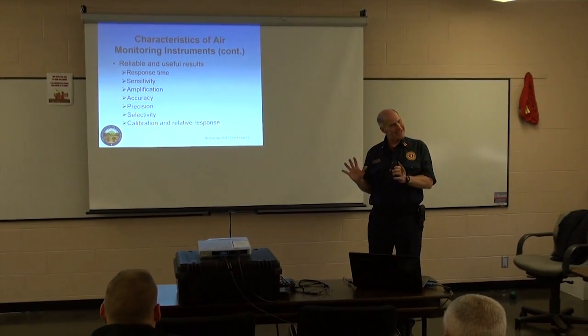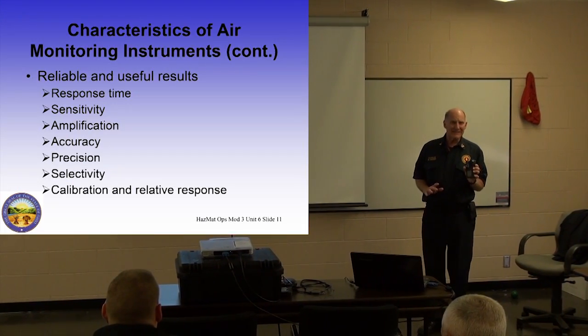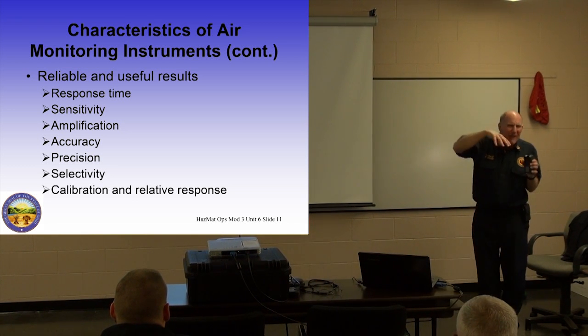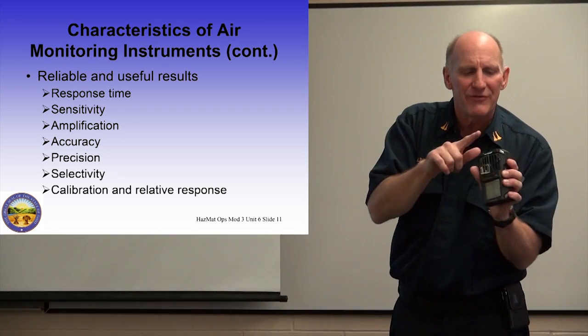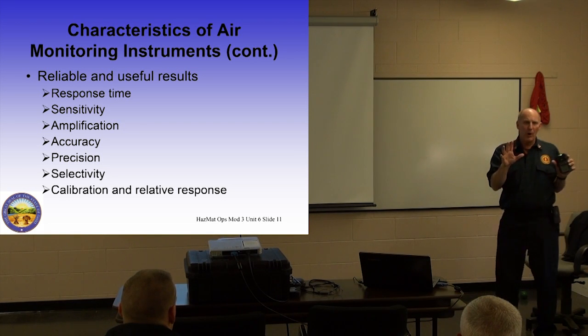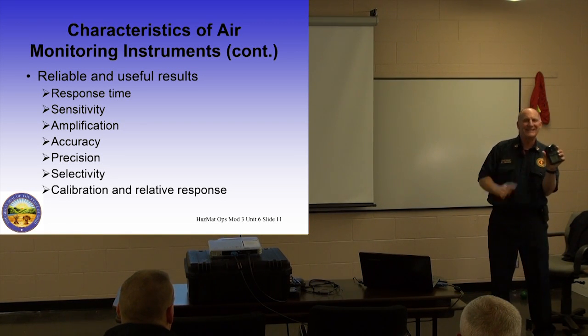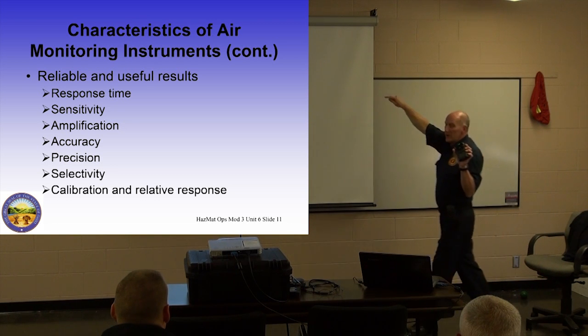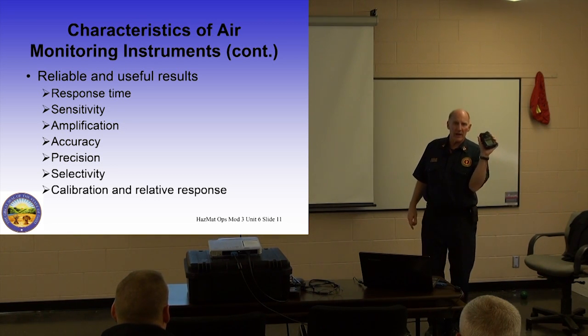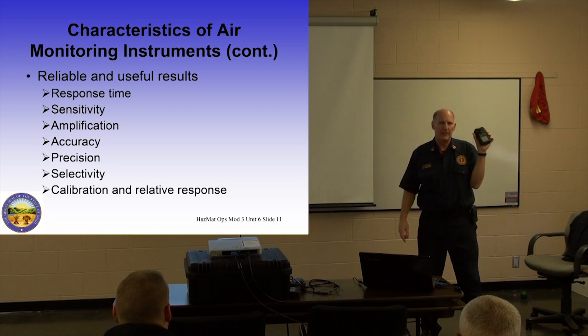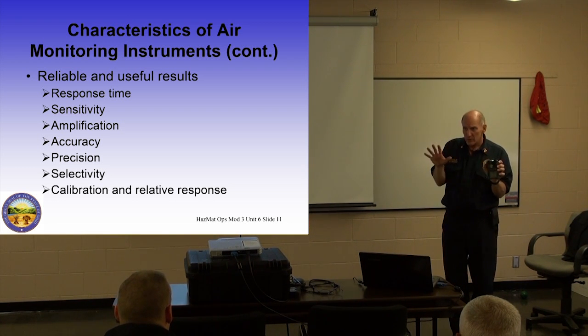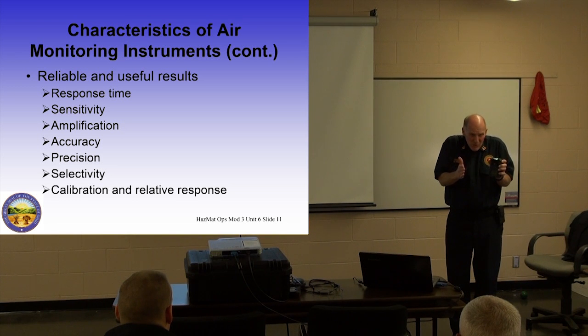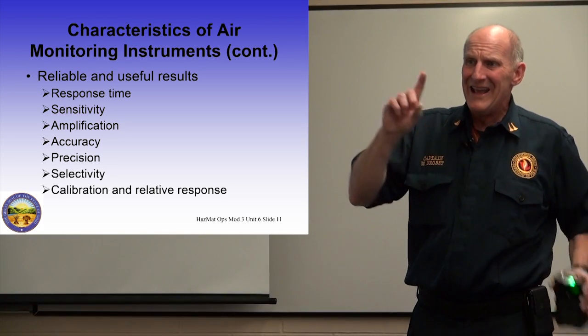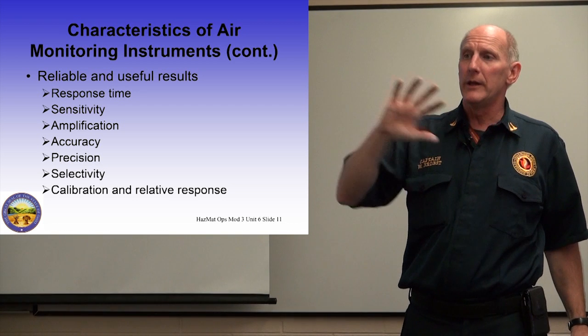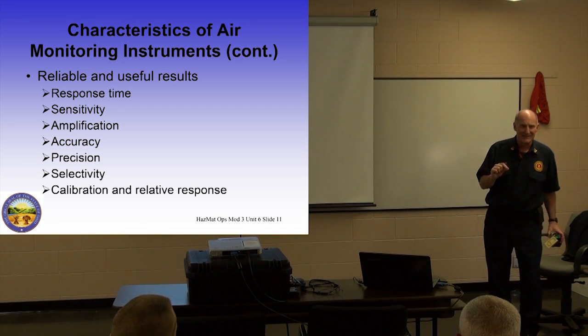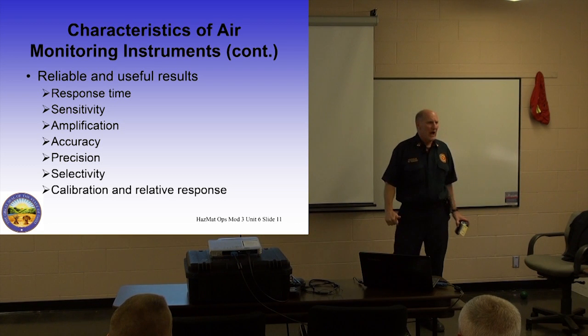Sensitivity. How sensitive is it? Sensitivity is really telling you how many parts in a million parts of air can this smell? How many parts of a bad chemical in the air does it take to get it to change? Okay, 3 of the sensors on this, carbon monoxide, hydrogen cyanide, and H2S, is relatively sensitive. It measures in parts per million. So when I get a reading of 1, it's telling you there's 1 part in a million parts of air. So that's sensitive. But the O2 meter is not sensitive.